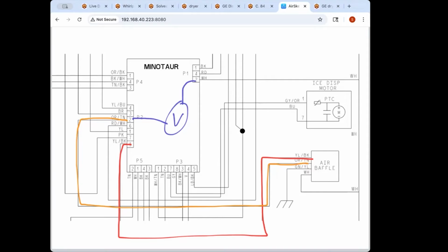And the position switch is just not changing state. Right. So the board is not getting the feedback it's looking for to tell it, okay, yes, the damper has closed or the damper has opened. So the board keeps supplying 120 to the motor on the yellow black line in the hopes that we'll eventually get a signal telling it that the damper has changed state.